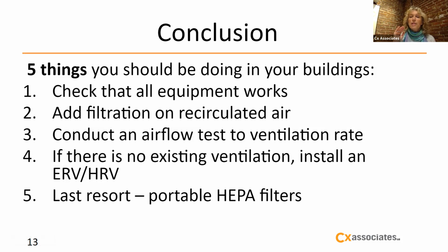If the air handling unit that you have has recirculated air, you want to filter the recirculated air. That means putting in a MERV 13 filter. And once you have those 2 things established, ask a mechanical contractor or a commissioning agent to conduct an airflow test to see how much ventilation air you have already, and to calculate how much ventilation each one of your spaces needs.